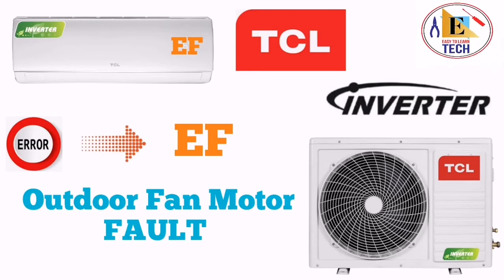And if the resistance of your fan motor is good, then you have to check the output power supply which is coming from your outdoor PCB. If the output power supply is according to the fan motor capacity and the power is coming out, it means your PCB is good. And if the power is not coming, if it's not giving the DC power, it means your PCB is faulty. You need to change the PCB and your unit will be in working condition.